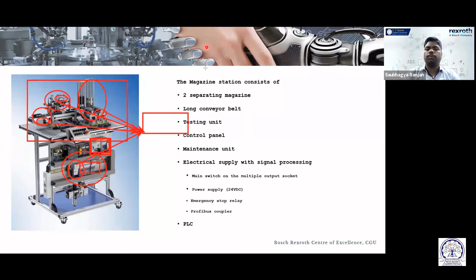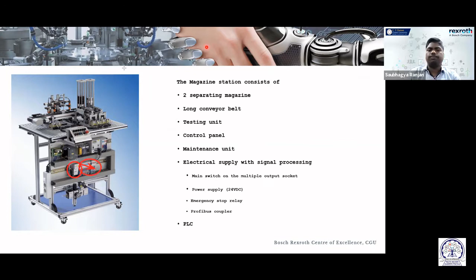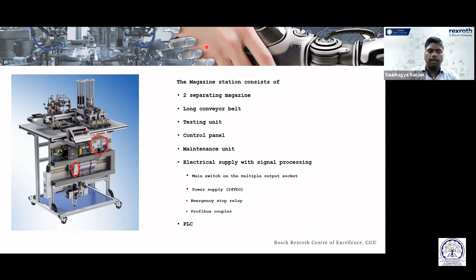Understood? Except your onboard module and inline module, what we do, we keep these input output modules in a particular point, then we connect some Profibus module which will receive the data from PLC and communicate with PLC and give signals accordingly to these IO modules. Sir, it is acting like a hub, you can say. Yes, your main PLC is acting like a hub, or you can say like a master. These are the slaves under it. This main PLC, you can say, is your master configuration or server, and these are the clients like this. All need to communicate with the main PLC or master PLC.